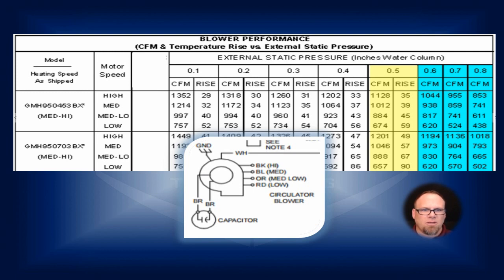400 CFM per ton. Now, what I like to do is when a system is brand new and I'm installing it for the very first time, I like to check the static pressure on each of those fan speeds and write it next to the fan speed. So that way, one, later on, somebody knows that it was done. And they see the values, they see the work done, they see the penetrations, they know that I did my job. Two, it allows me to come back and make adjustments knowing what those static measurements are. I can quickly see all the CFM values that correlate to the static measurements.